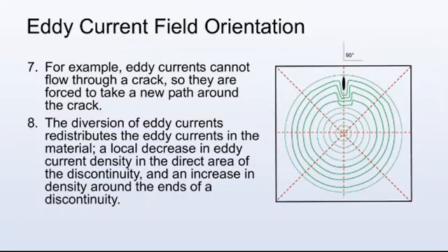The diversion of eddy currents redistributes the eddy currents in the material, which causes a local decrease in eddy current density in the direct area of the discontinuity and an increase in density around the ends of a discontinuity.